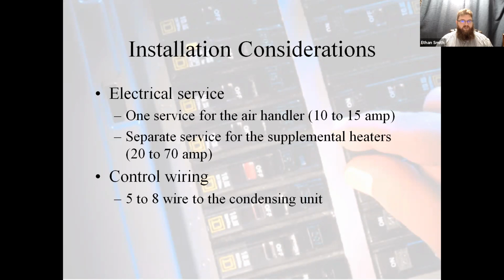I actually have a unit on my shop where I've got 3 strands of 8 conductor run to it. We had to do that because of some experimental controls that the factory was trying out on that unit. And boy, I'll tell you guys, it's sure a nightmare to have multiple of the same color at the outdoor unit. Just make your life easy, guys. If you've got the option, run a spool of 8-strand out there. Keep your life simple.